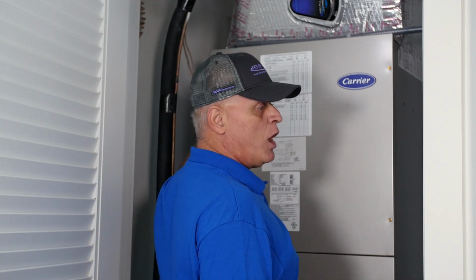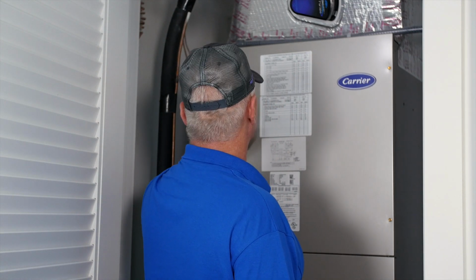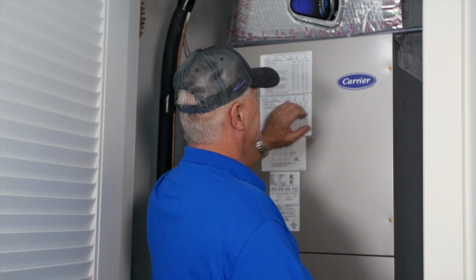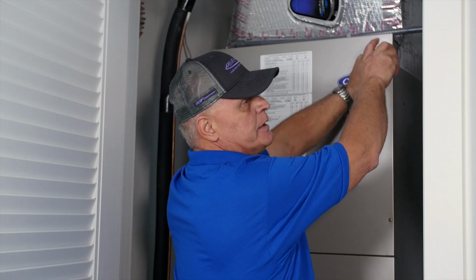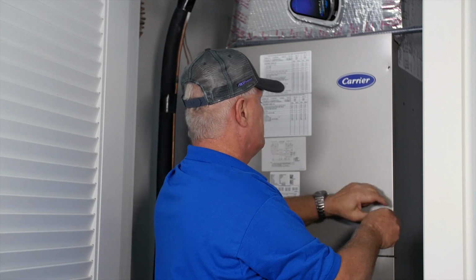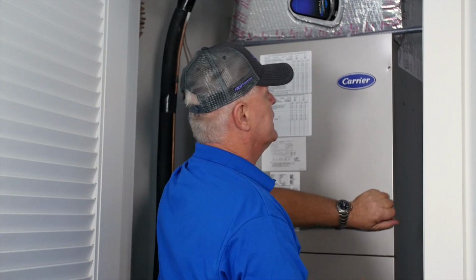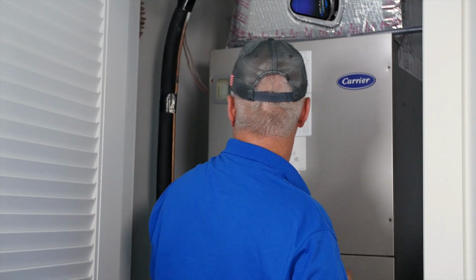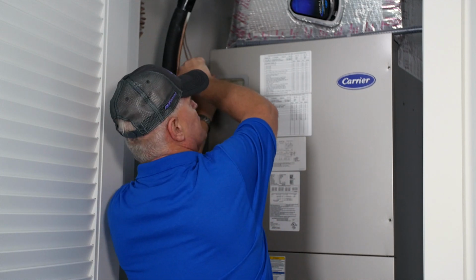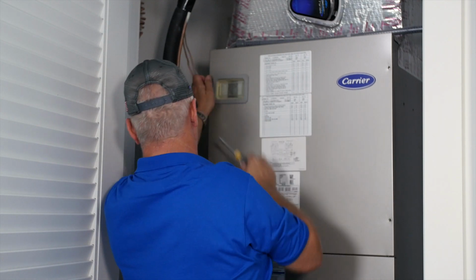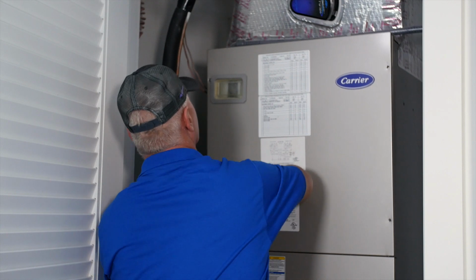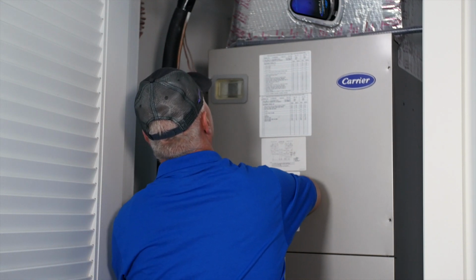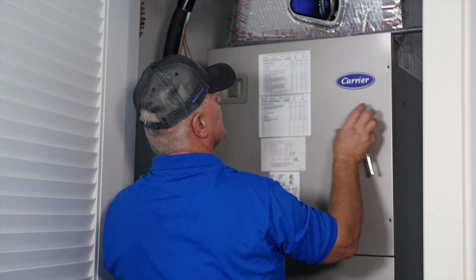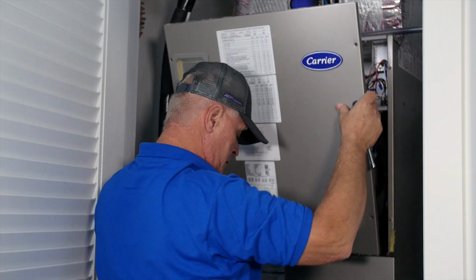First things first, always disconnect your power. On this unit, we're disconnecting it right here. It does have a disconnect as well, but this is a good positive disconnect for the power. Never work on a unit while it is energized. This is a standard air conditioning unit.